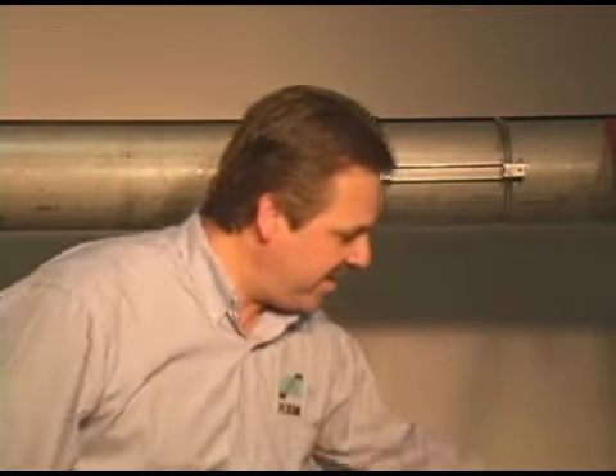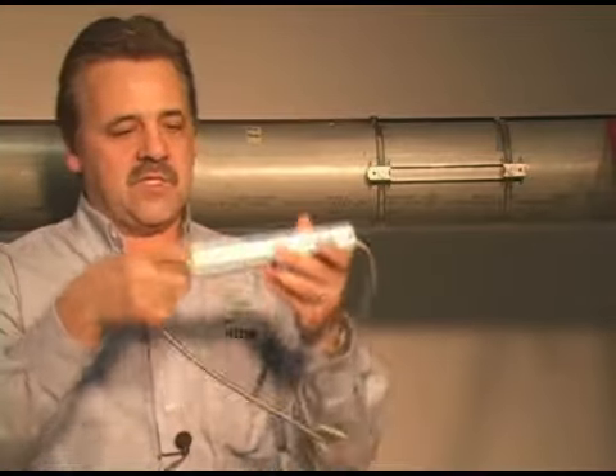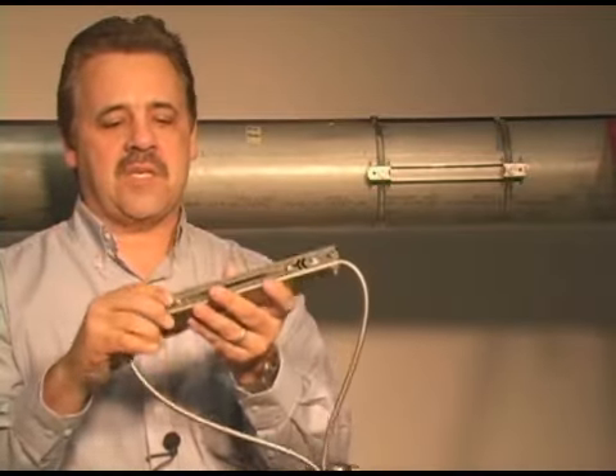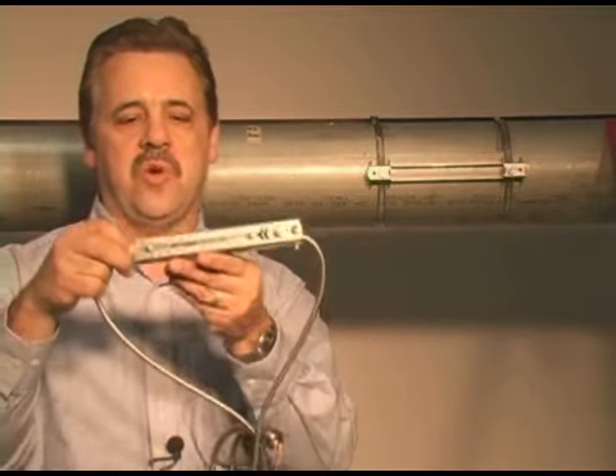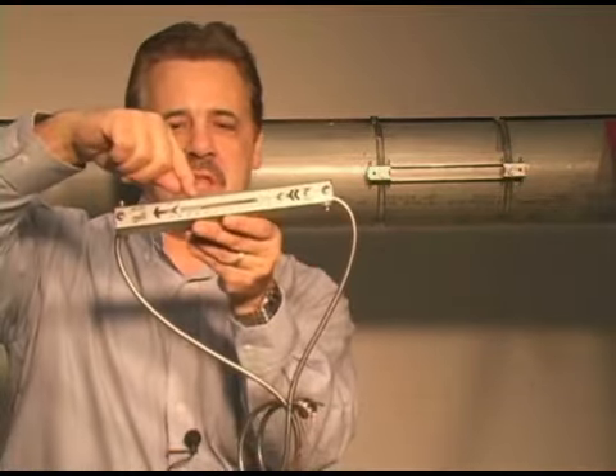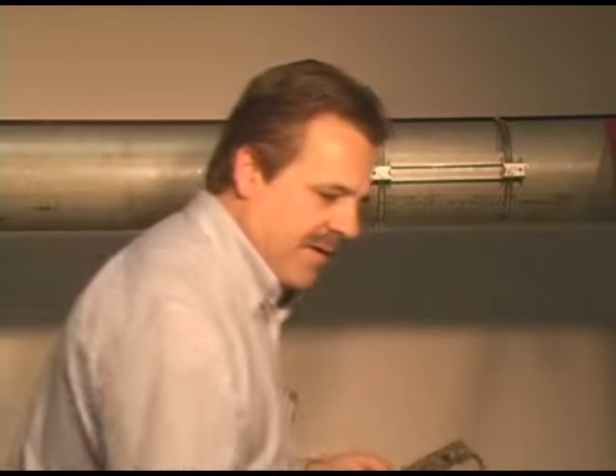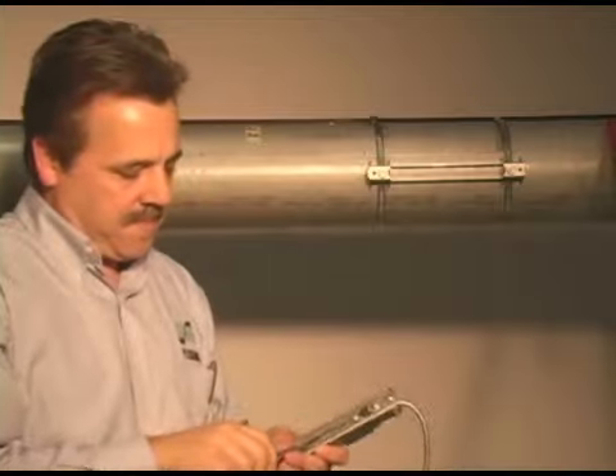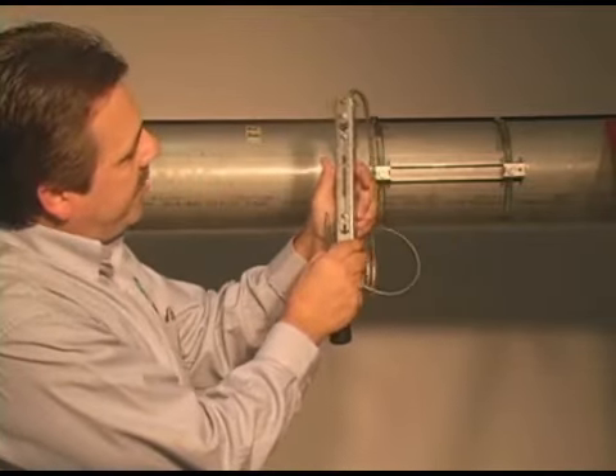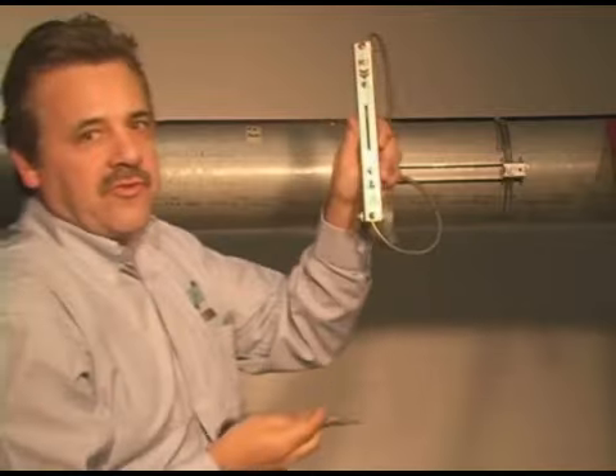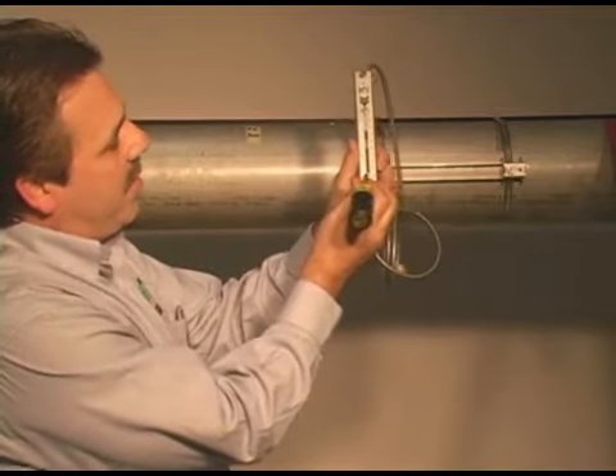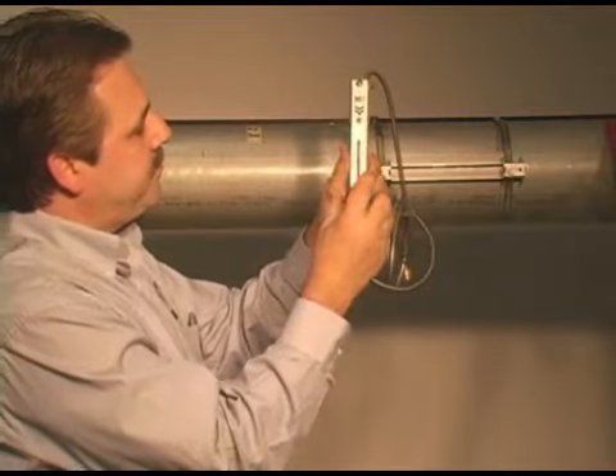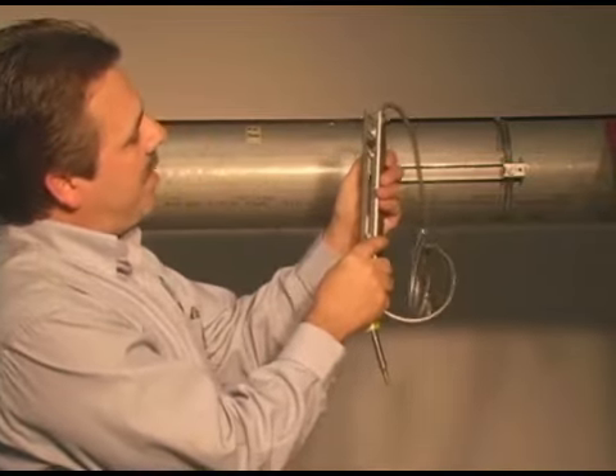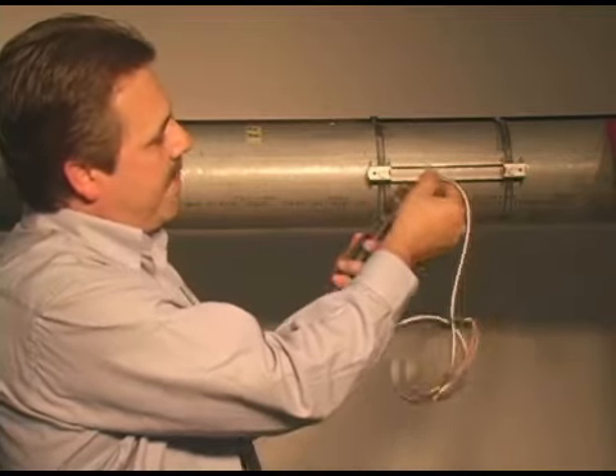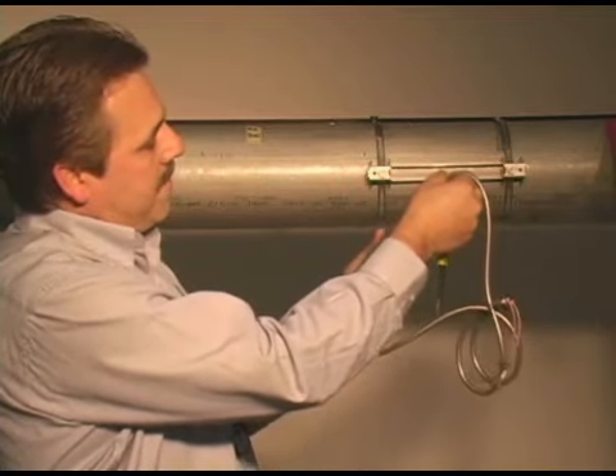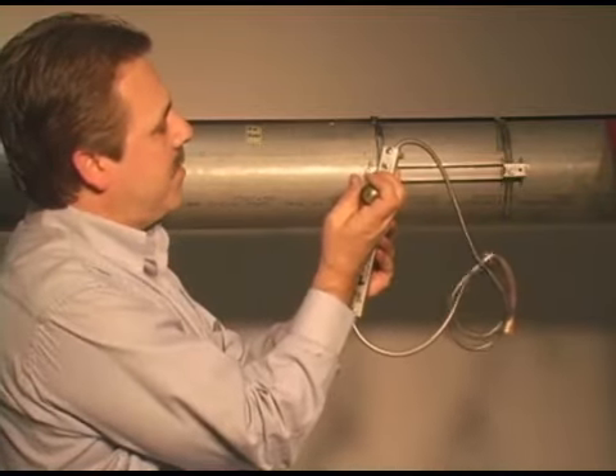Okay, now we're going to get the upper part. Now here we have to space this out to the spacing distance. Now let's say that the spacing distance was 2 inches. So we have a 0 mark here. I'll set this at the 1 inch mark and this at the 1 inch mark. I tighten it down with the screwdriver. Okay, so you'll see that there is a metal plate here. You may not be able to see that, but there's a metal plate here that will line up with the 1 inch mark. Okay, and I'll do that with the other transducer. Okay, and we'll line up with this 1 inch mark.